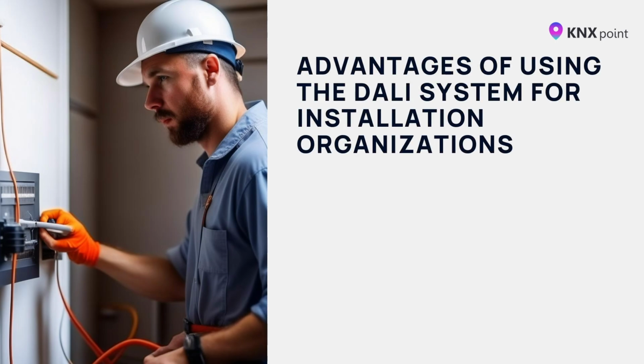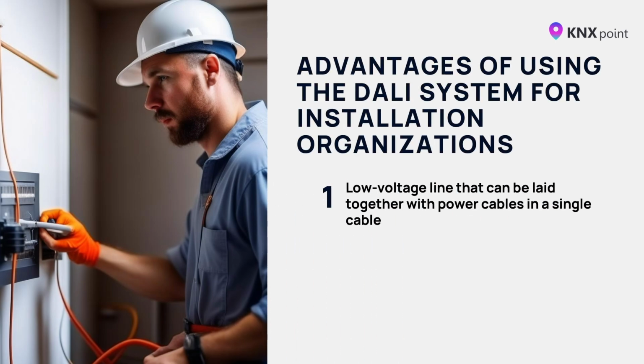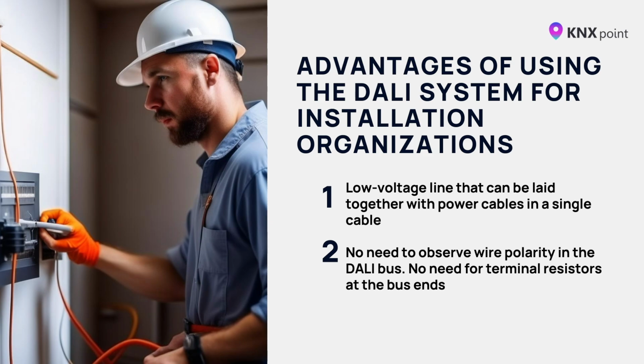Advantages of using the DALI system for installation organizations: low voltage line that can be laid together with power cables in a single cable. No need to observe wire polarity in the DALI bus. No need for terminal resistors at the bus ends. Simple configuration of lighting control scenarios.